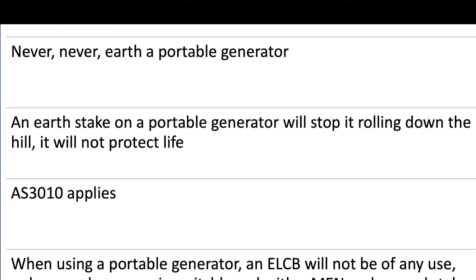But with my little Honda 1 kVA generator, I never worry about it because I always use proper leads and don't let it get covered in water and stuff like that. Having said that, for semi-permanent and permanent genset installs, you can, that's quite okay to put them in, but the law and the rules say you've got to switch the neutral at the same time when you change over switch. Okay, you can't leave the neutral connected. That's not a good practice. So that changeover switch switches both the active and neutral. That's the rules.